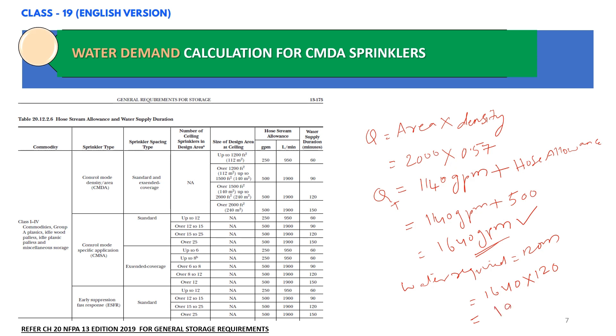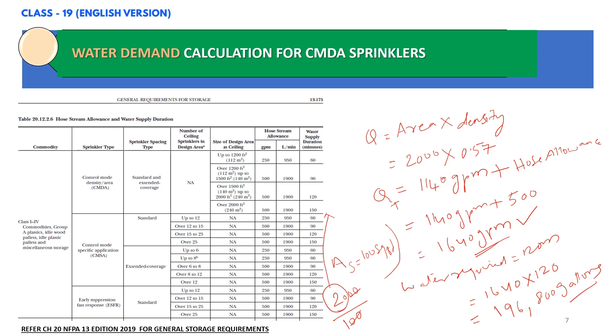The water required will be for 120 minutes duration. So the water quantity will be 1640 multiplied by 120 minutes, which gives 196,800 gallons. One more thing: the area of one sprinkler as per NFPA 13 for CMDA sprinklers will be about 100 square feet. So based on this, the total area of sprinkler operation is 2000 divided by area of one sprinkler, which gives about 20 sprinklers. We need to use 20 sprinklers.